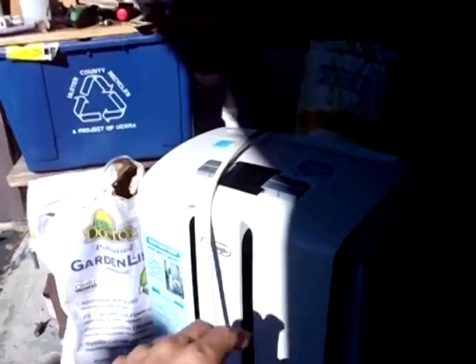And the only other thing I'm going to say is I also saw a spec on here in the back, it said about the pressure, the low and high pressure, and I think it said the high pressure is like 490 psi and the low pressure is like 300 psi. That is not realistic. You would never have a low pressure of 300 psi. It could be that that's what the unit is tested for in terms of pressure. You know, they pressure test it to make sure it's not leaking, maybe.